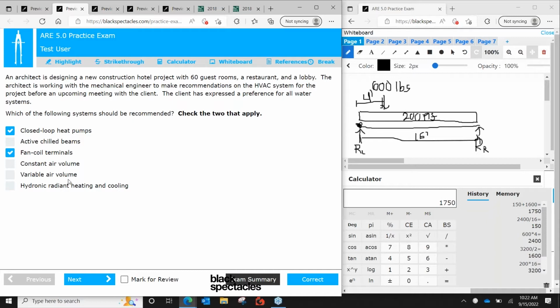So for constant air volume, abbreviated as CAV, it is similar to VAV in that it is a centralized air system with heated or conditioned air ducted from a fan room to each floor and room. However, the volume of air that is supplied to each room is universally controlled, making it a better choice for a convention center or assembly space. Since each room is unable to adjust the air individually, this is not a good option for hotels. We would not select constant air volume in this scenario.